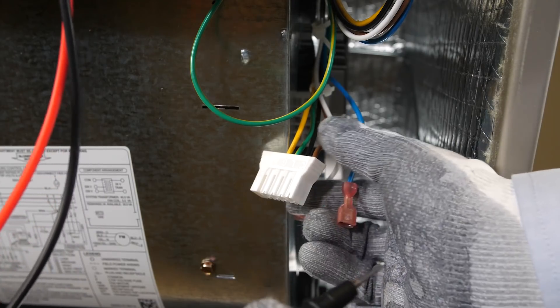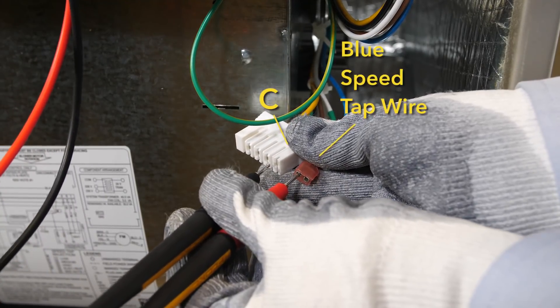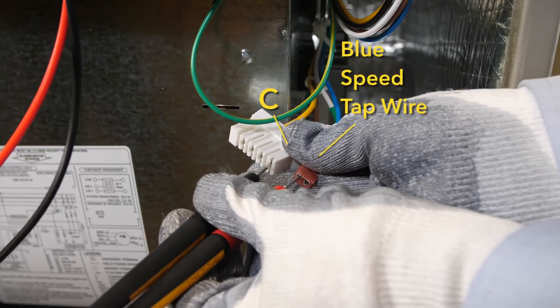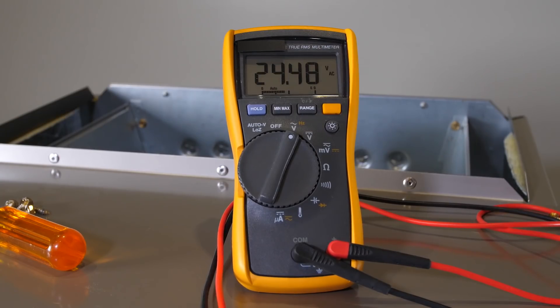Check low voltage power between C on the white plug and the blue speed tap wire. Confirm that you have 24 volts AC.